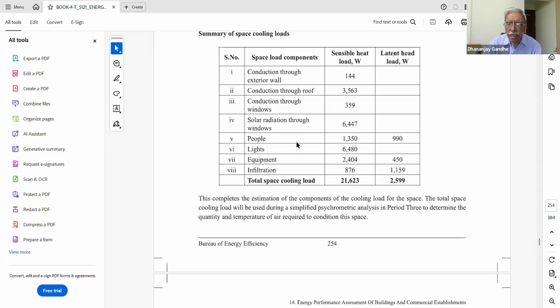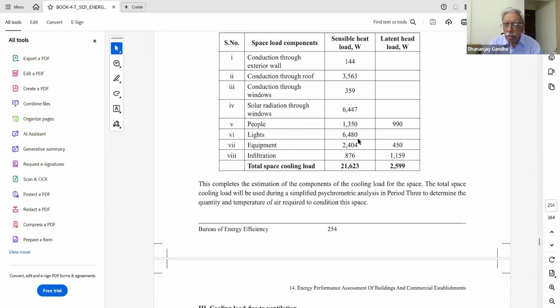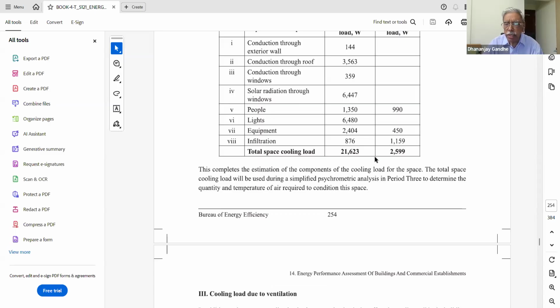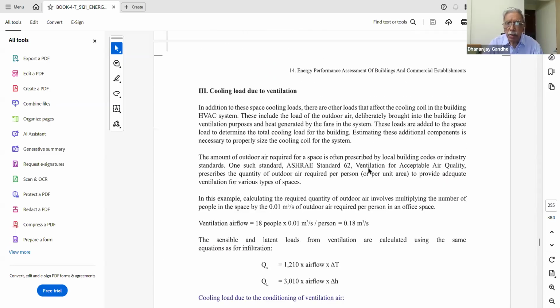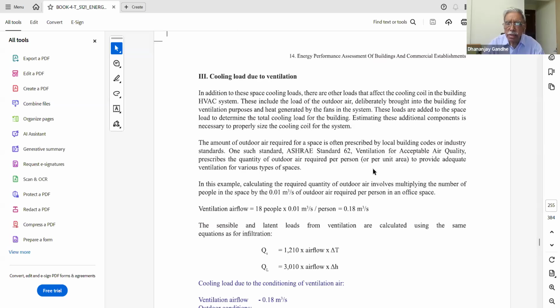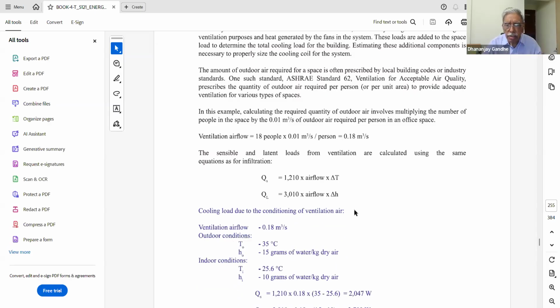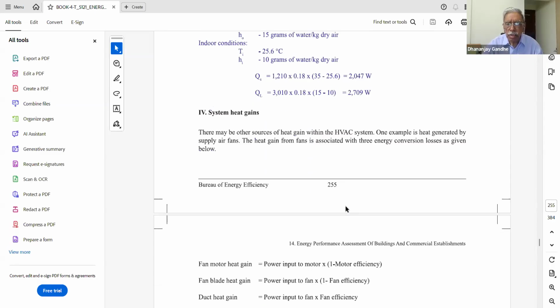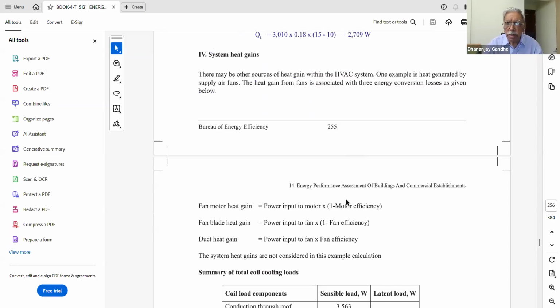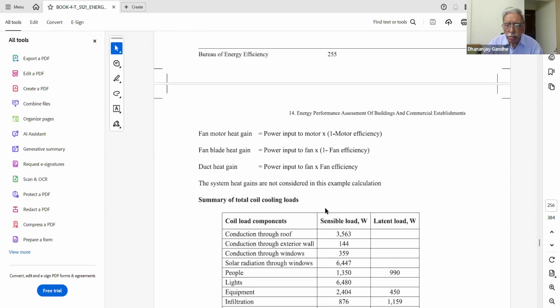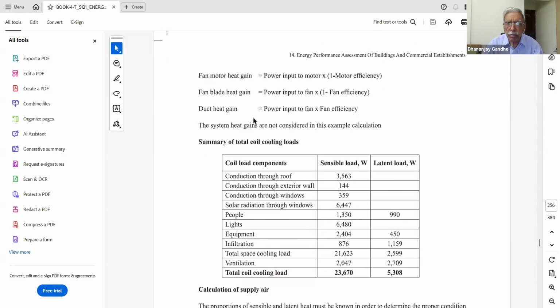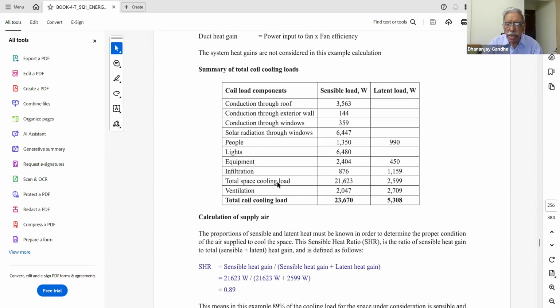Then the heat gain from the people is calculated. Procedure calculations are given above. Lights we also calculated. Equipment load we calculated. Infiltration we calculated. So this is a summary of the space cooling load. Okay. Add to that the load due to ventilation. That means the ventilating fans will be there, and some others, so their loads are to be added to this, and also the system heat gains because of the equipment, that is because of the motors, the fan blades, the ducts, and so on. So that is to be added. So this is called the ventilation load. So this gets added over here.